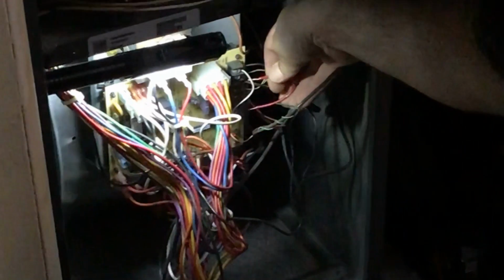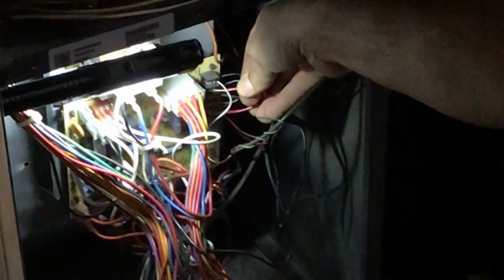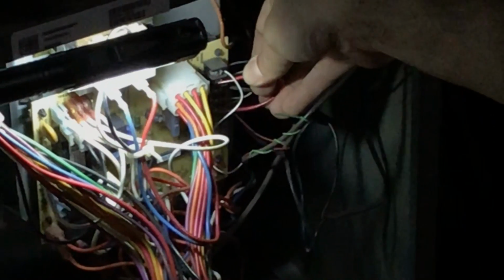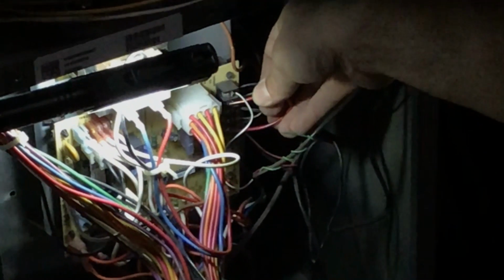So if you have a bad board or a thermostat, the wires here, your green wire controls your fan, and your red wire is your power wire. So if you have an inoperable fan, in addition to everything I talked about in the last segment, the next thing you want to do, if you can see, is take a little jumper wire and touch your red terminal to your green terminal. And if your fan then comes on, then your problem's with your circuit board, or possibly your thermostat, and we'll get into that more as we work through the 24 volt aspect.